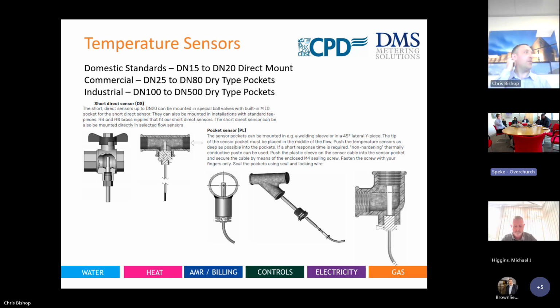It's not touching the flow of water. It will still calculate energy, but it will not capture the true energy of the water. You could kind of say there's a small air pocket inside. And we've done some trial tests over many years, and an error of about 1-2 degrees can happen. 1-2 degrees over a 24-hour period is probably not considered a lot, but over a year, over 10 years, you're not capturing that energy correctly. So it's very important to install a pocket on the MID design.